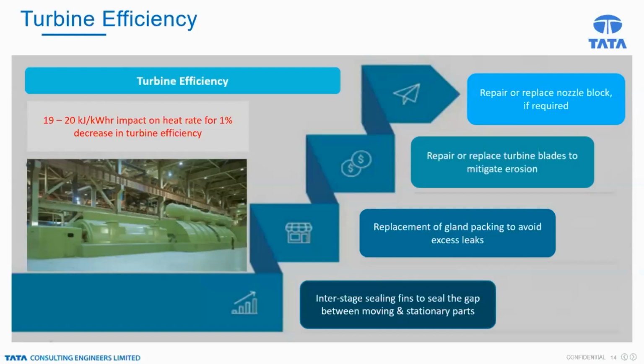To improve the turbine efficiency, we can do interstage sealing, replacement of gland packing, and repair or replace the turbine blades wherever heavy erosion has taken place. Obviously, probably not in the initial stage of operation, but after a few years, if required, we have to take care of the erosion, with a few blades to be replaced. That should be done, and repair the nozzle block if required. If we take care of these and maintain the turbine efficiency as high as possible, then we will be able to derive a better turbine cycle heat rate.